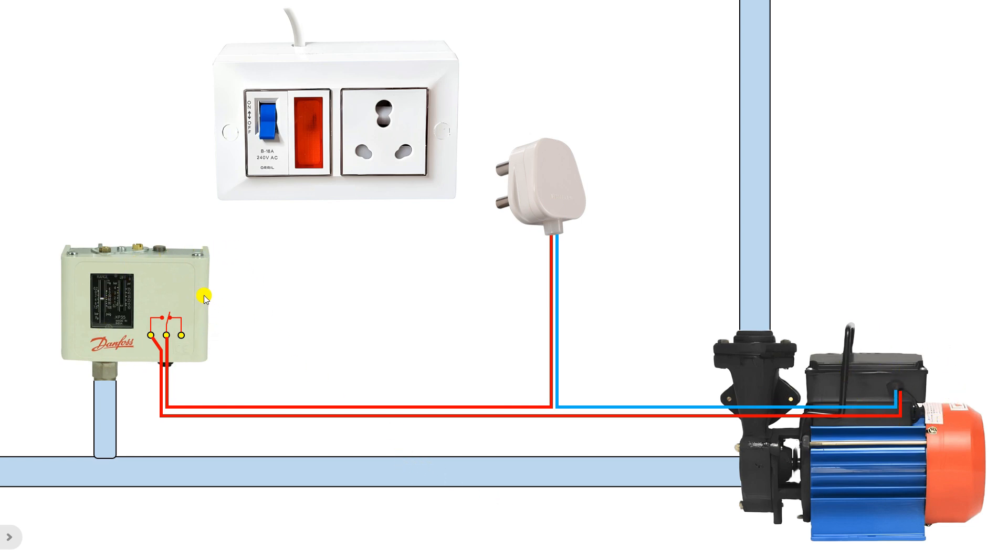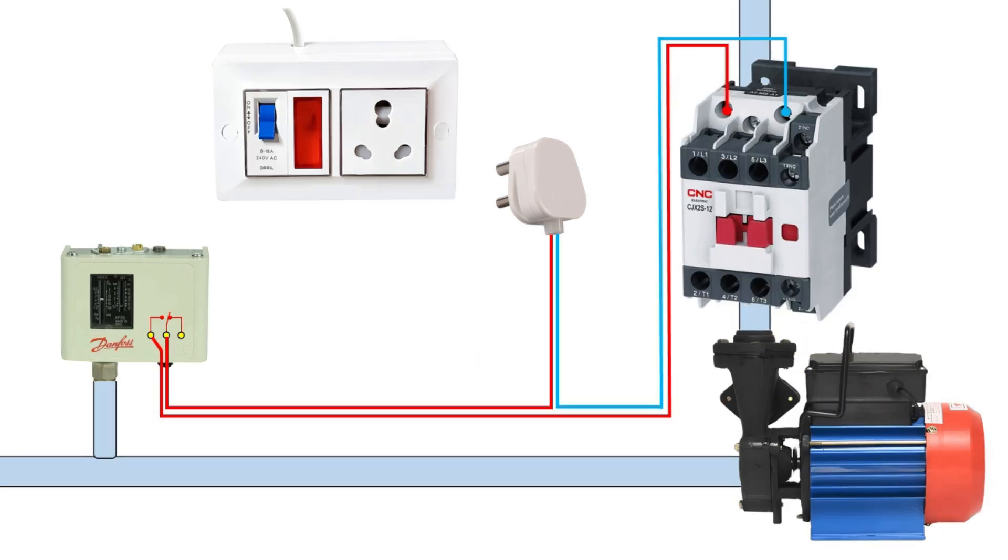If you use the contact of this pressure switch directly, then you have to make sure that the current does not flow more than the rating. If the current rating of the machine or motor near you is high, then use a contactor in this condition.